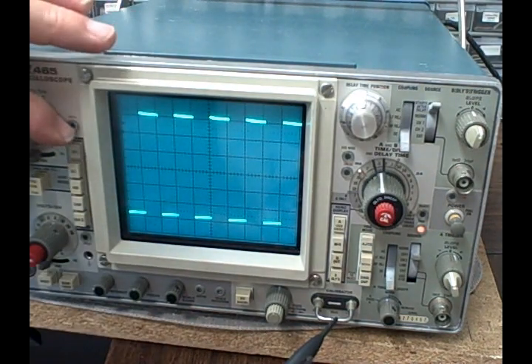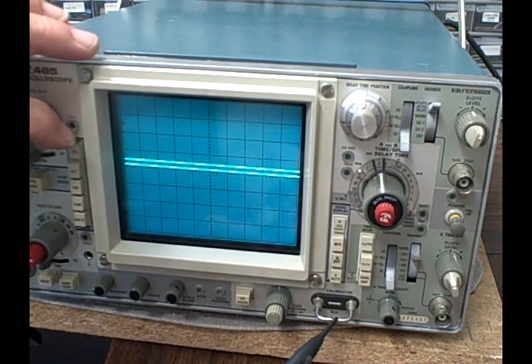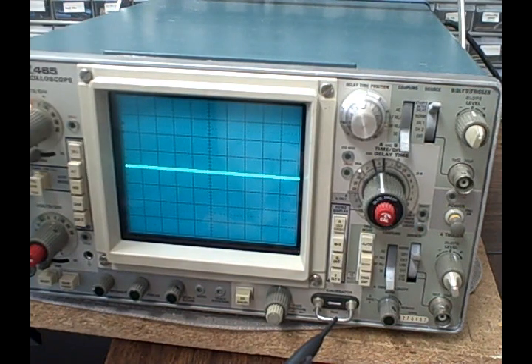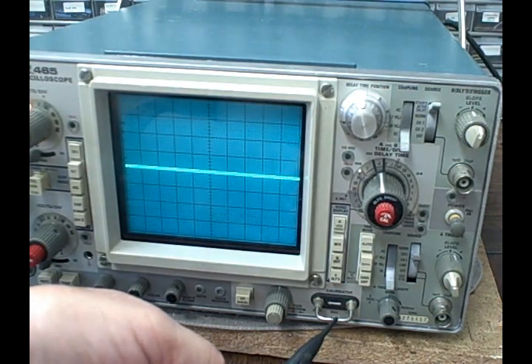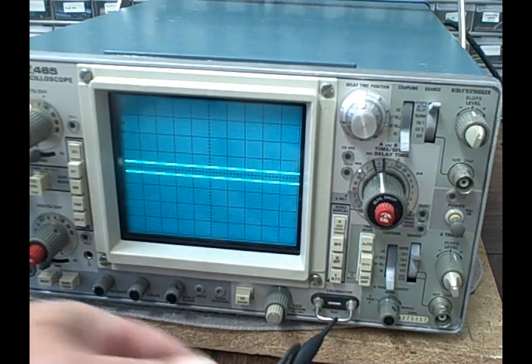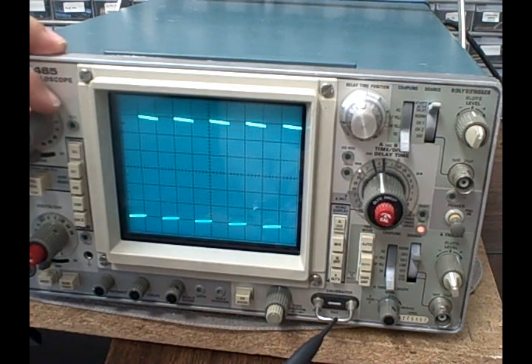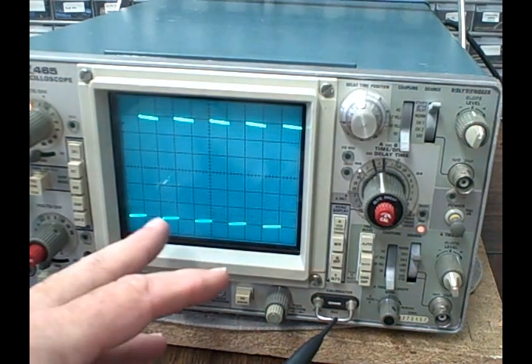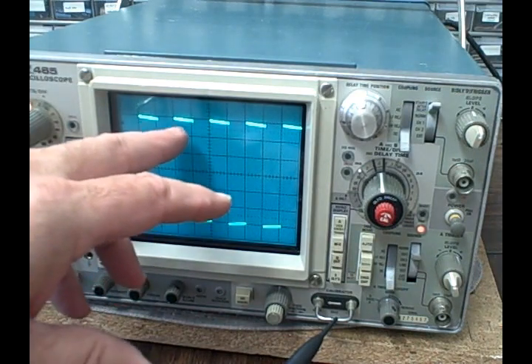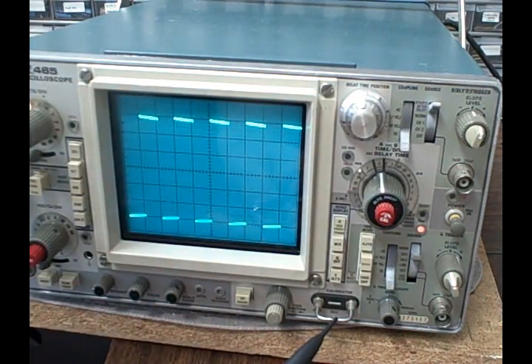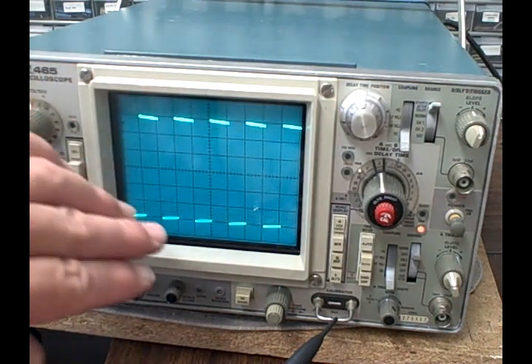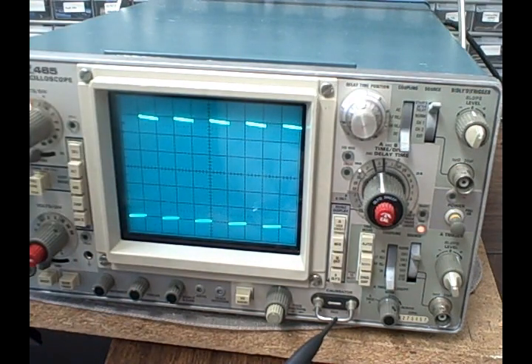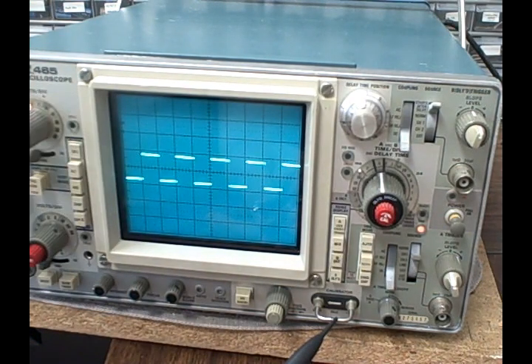Now if I put my probe back up, make sure we're zeroed, and then I put my probe into the times 1 position, 50 millivolts per division. Let's go 50. We were at 5 earlier. So here we are, 3 up, 3 down, that's 6. So 6 times 50 millivolts is 300 millivolts. So we've got a 300 millivolt peak-to-peak square wave. And that's what we wanted. So the calibrator is working fine, and that's basically how you'd use it with the probe.